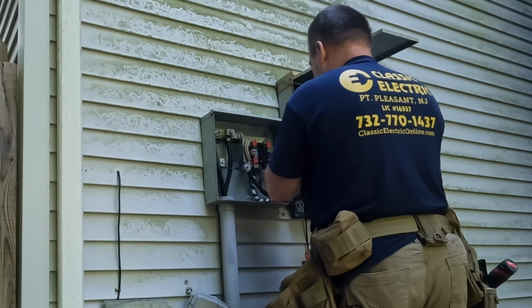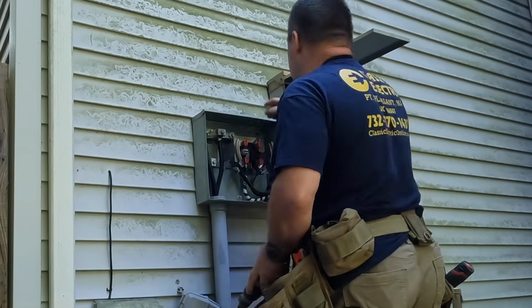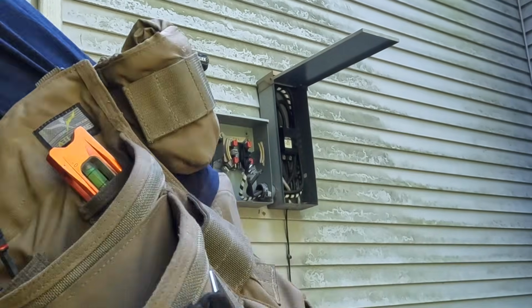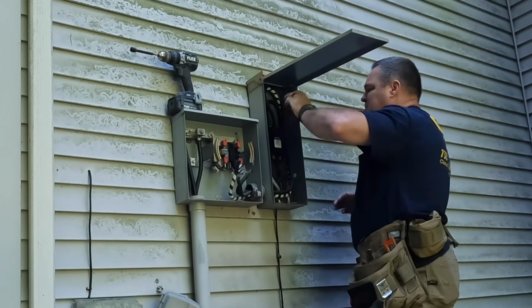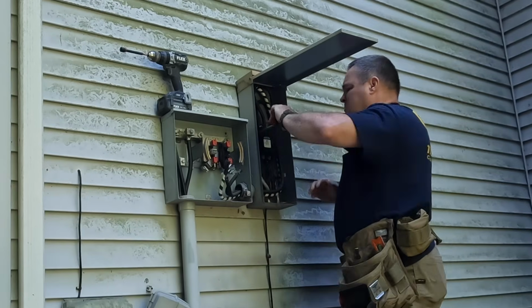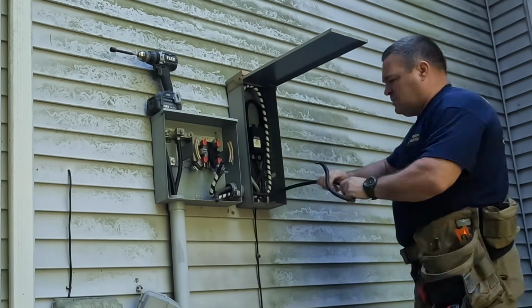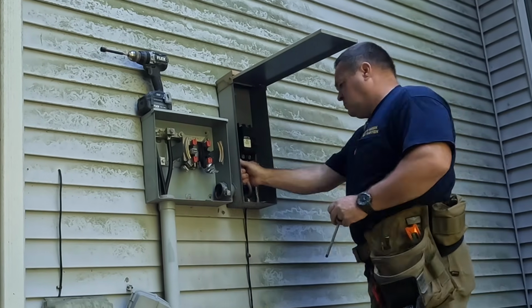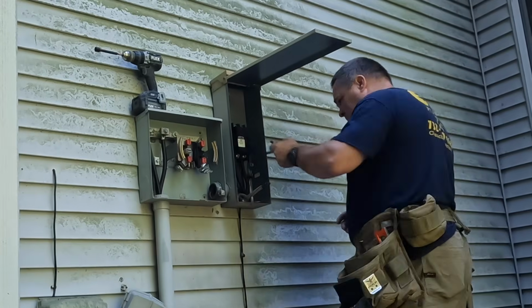Anytime the wiring, the panel, the main disconnect is not directly behind where that meter is, you're going to have to put this disconnect in. And the reason why we did that before the required disconnect is because the fireman would have to find out where that main breaker was if it wasn't on the immediate opposite side of the meter.